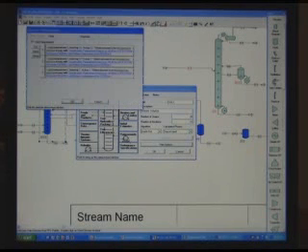And then the pump arounds, there are 3 of them. So one going from tray 14 to tray 13. Again, you use 2 trays because it doesn't really help if you put more than that in there. The return pressure is in PSIG. And then the duty is to be minus 40 million BTUs per hour. And the return temperature is 450.